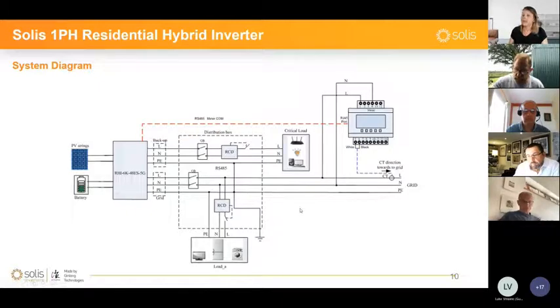Additionally, there's the backup port that I was mentioning earlier. Here, the inverter will have connected the critical loads, as we call them, that the customer might have, which can be linked here and be supplied in case there's a power outage. These loads can normally be supplied from the grid itself through the inverter when there is grid available. But otherwise, if there is an interruption, they can be supplied from the battery and PV side.